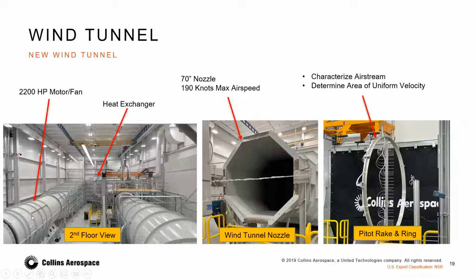So the motor and fan in this section generates the airstream towards the back of the room through the heat exchanger. Without the thermal management, the airstream in this facility gets warm very fast. If you think about a 2,200 horsepower motor fan for a RAT that at maximum requires 75 horse, all the rest of that when you're operating at top speed is thermal losses, frictional losses in the shell. So that heat exchanger is pretty sizable, requires a lot of water flow to be able to maintain air temperature, both in the facility and just for the airstream.